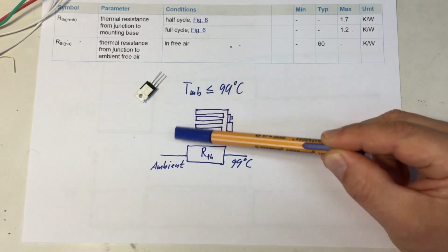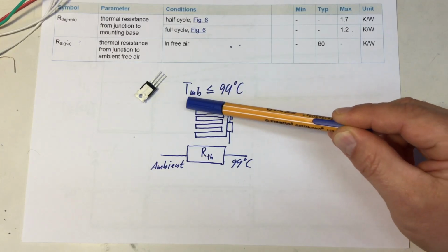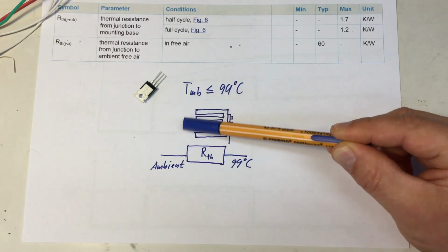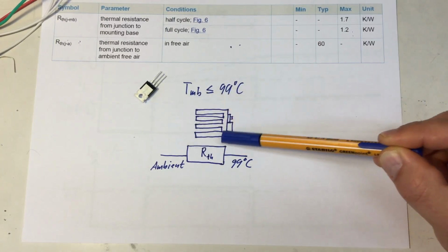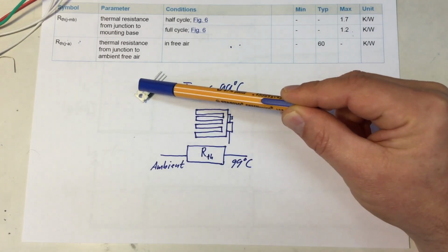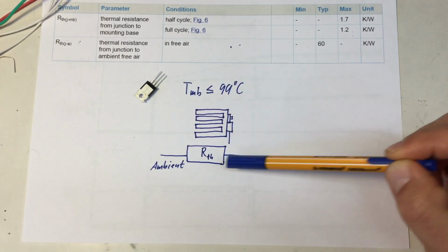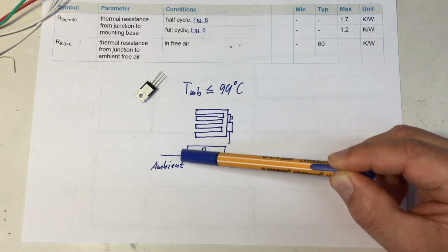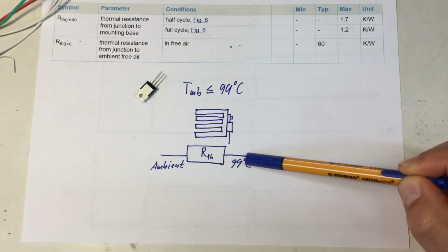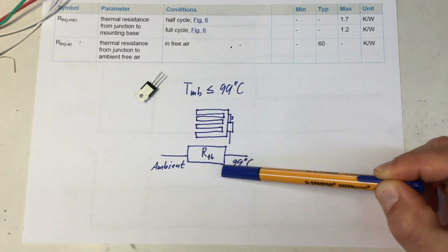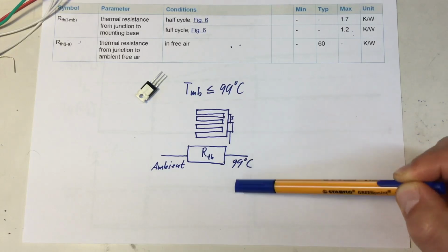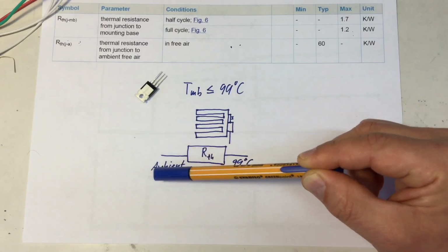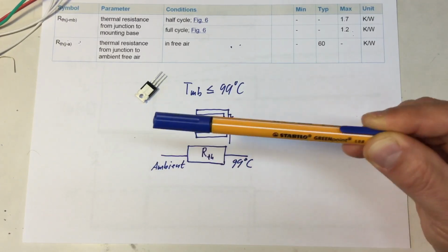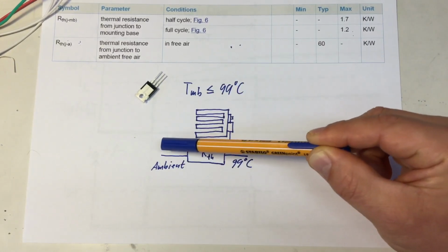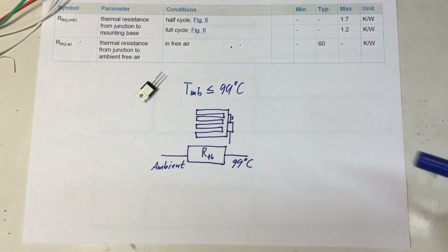So you can simplify your thermal design and only have a look at the heatsink you are screwing at the back of your TRIAC, take the heat resistance of that, assume allowed maximum of 99 degrees Celsius on one side, and on the other side your ambient temperature, so maybe 40 degrees Celsius.